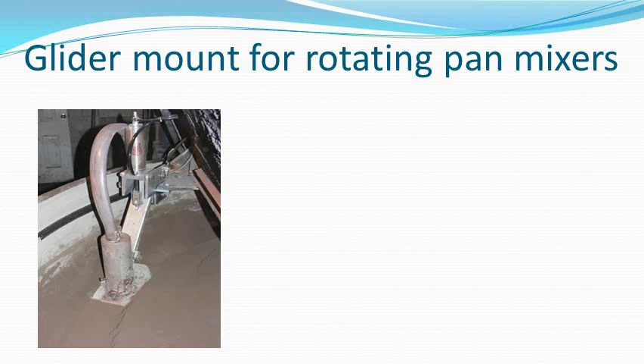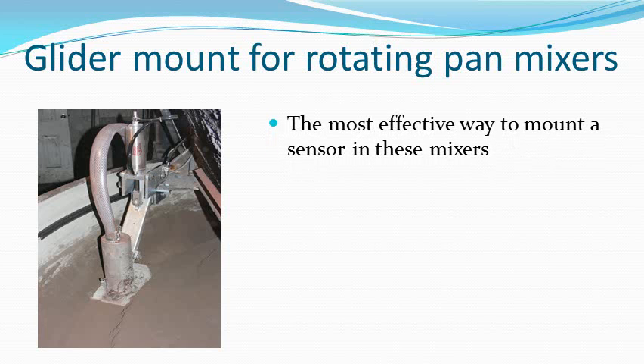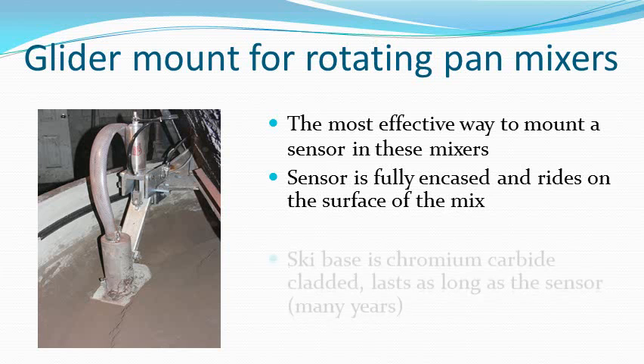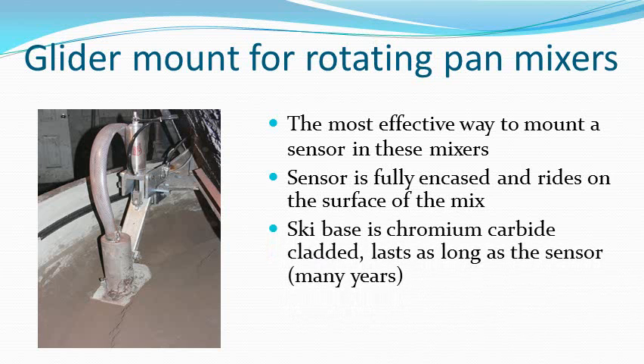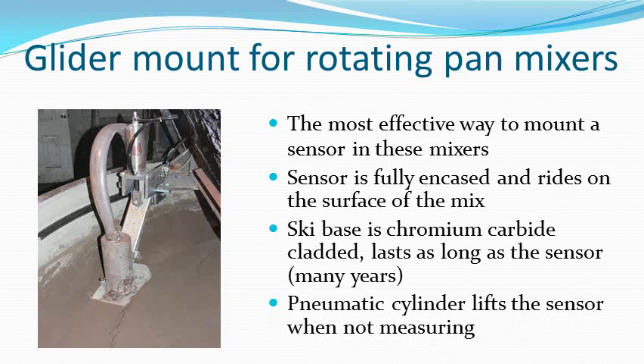The Glider mount is a recent development for use in rotating pan mixers. The problem of varying depth of material is solved by a pantograph arm that allows the sensor to ride on top of the mix while keeping it parallel to the surface. The ski base is chromium carbide cladded, which is as hard as the sensor faceplate, giving many years of life. A pneumatic cylinder raises it when not in use.